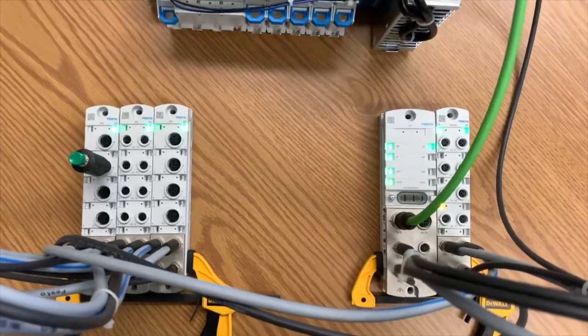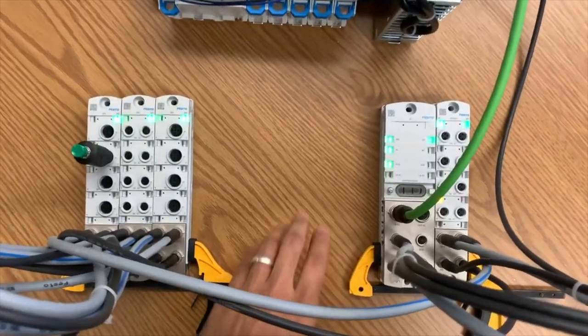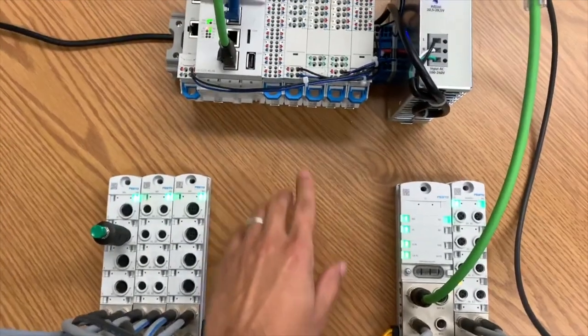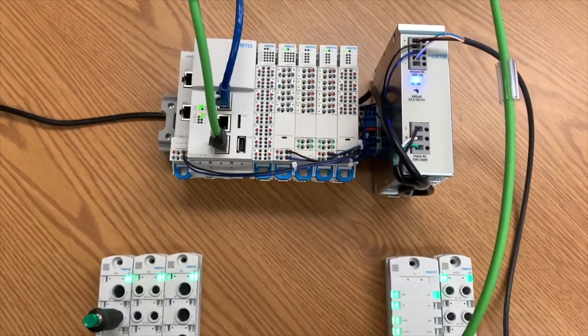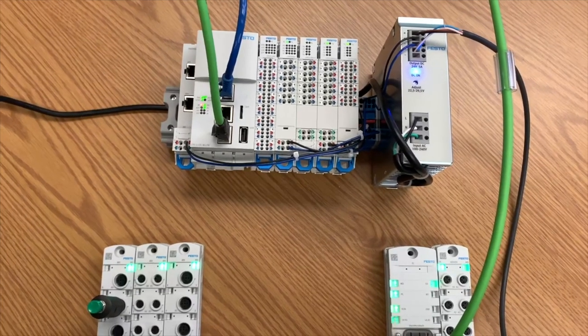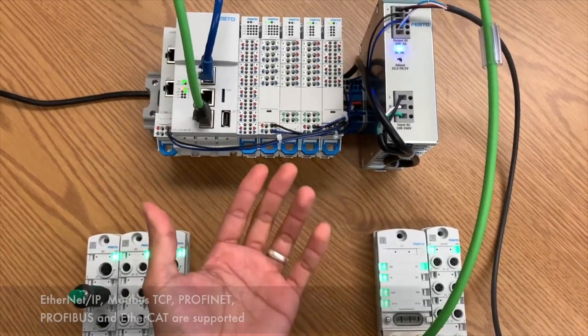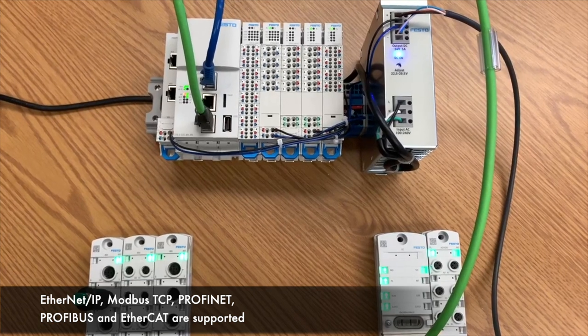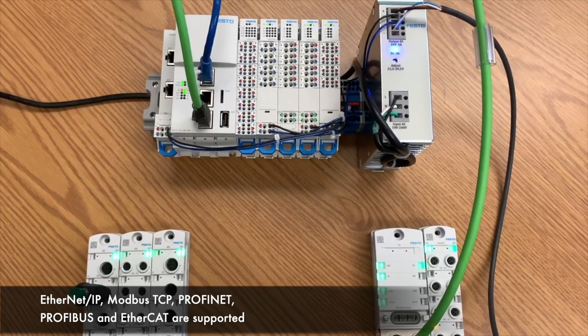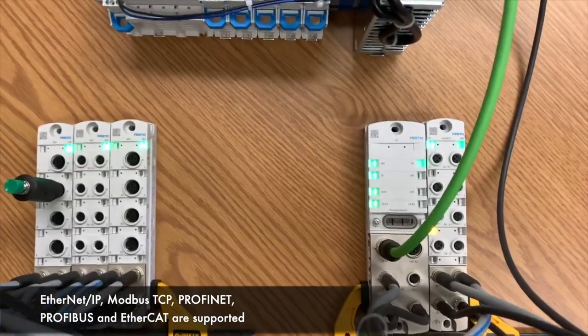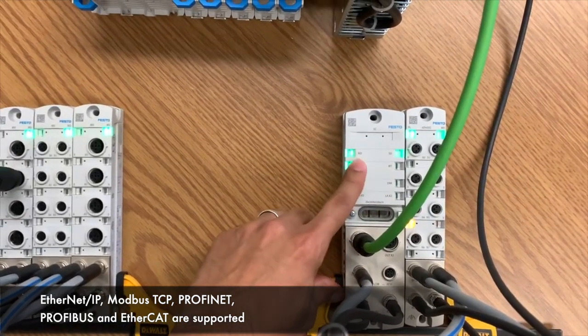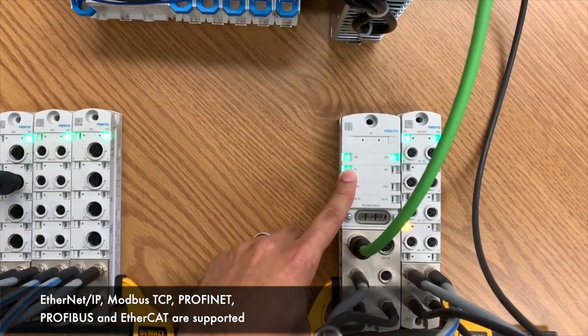The nice thing about this is that you can keep the infrastructure below the PLC. So for example, this could be a Rockwell PLC, it could be a Siemens PLC or something different. We can support Ethernet IP, EtherCAT, Modbus TCP, and Profinet. So the only thing that I would change is this module to be able to communicate to something else.